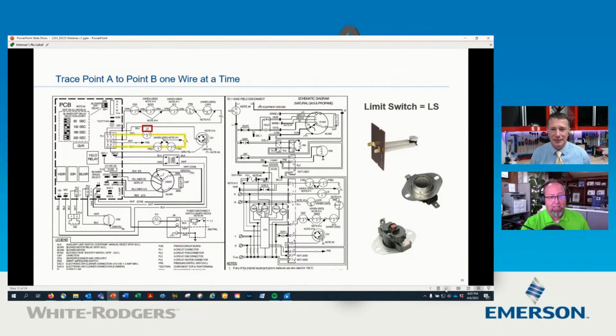Most furnaces have these, though how they operate can differ. Some are just monitored, and if there's an open switch, it won't allow the sequence of operation to start. For a number of years, Carrier put this circuit on a normally closed fan relay. So when you powered the furnace up, the blower started blowing and wouldn't shut off until it recognized the circuit was complete. When it saw the circuit complete, it energized the relay, opened the normally closed contacts, and shut the blower off.